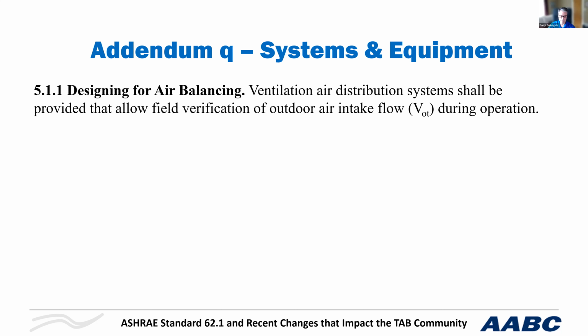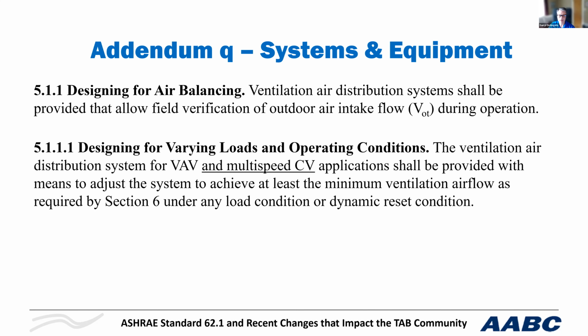Another thing I'd like to discuss here, and since the poll question happened, it didn't advance. Okay, is in 90.1, which is the energy standard. In 2014, manufacturers started producing equipment to reflect a change, which was to have variable speed, constant volume equipment, or what they referred to as multi-speed constant volume. So really, in commercial equipment, there's no such thing as constant volume equipment. They'll refer to constant volume all the time. What this means is the speed is always changing with the load. As we approach the temperature in the space, with modes of operation such as cooling, heating, or ventilation, this constantly is changing the balance point to maintain the same ventilation rate.